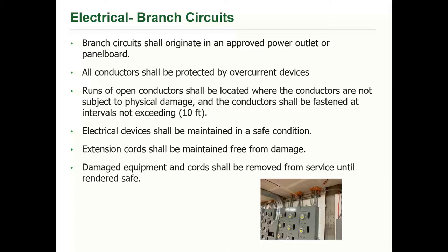But according to NFPA 241, all branch circuits need to originate in an approved power outlet or panel board. All conductors need to be protected with overcurrent devices. Runs of conductors should be located where they're not subject to physical damage, and they should be fastened not exceeding 10 feet apart.